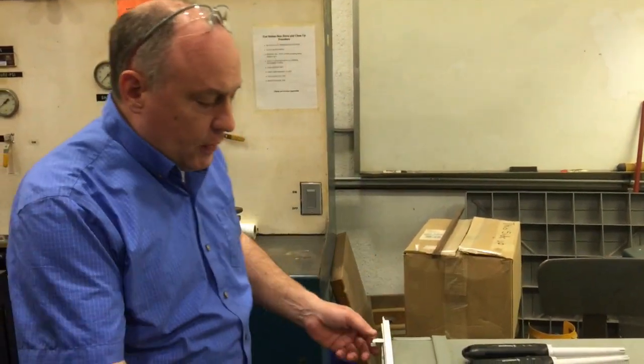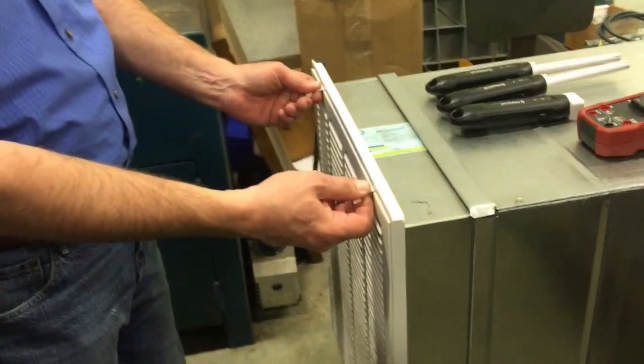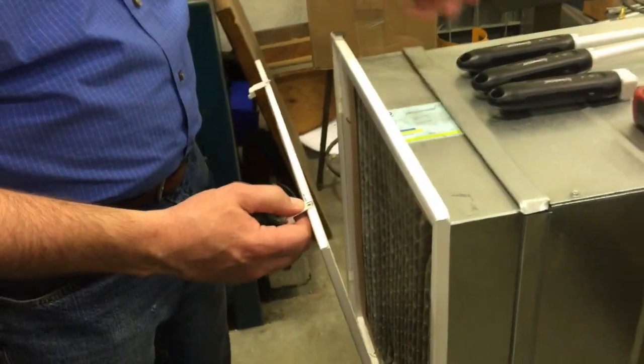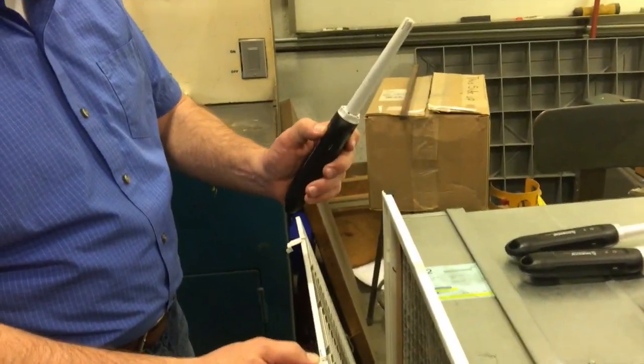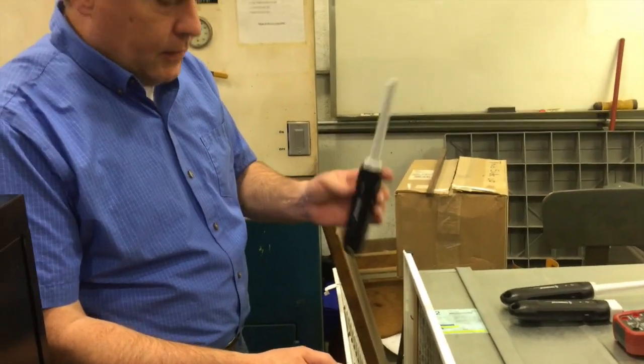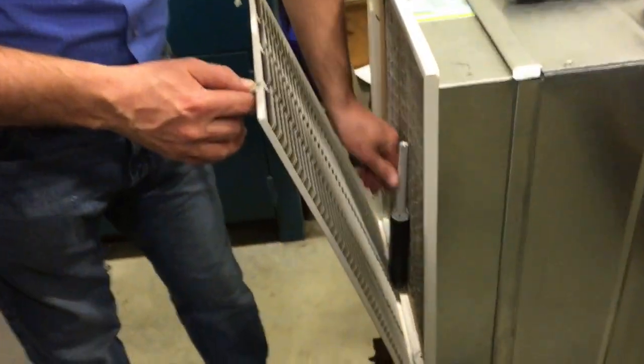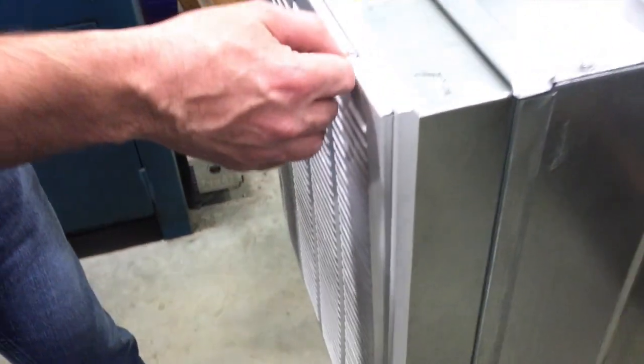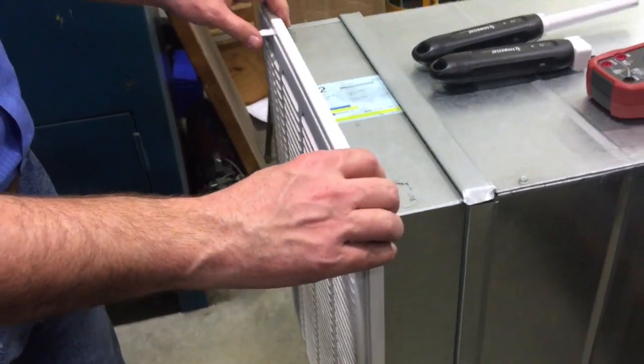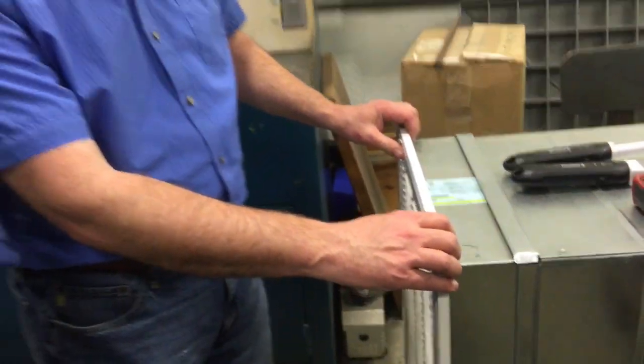So the first thing I want to show you here is one of the mistakes that a lot of people make. They forget that our probes are actually wireless, and it's really very simple to take the probe, put it inside a return air grate, go ahead and close that grill up there instead of having to drill a hole in the return or supply.